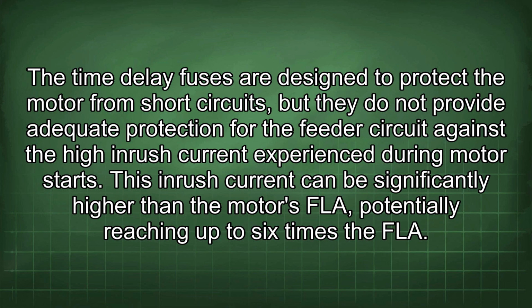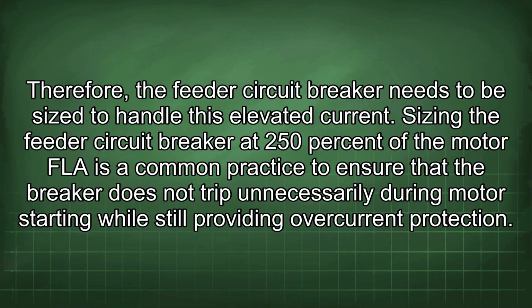This inrush current can be significantly higher than the motor's FLA, potentially reaching up to 6 times the FLA. Therefore, the feeder circuit breaker needs to be sized to handle this elevated current. Sizing the feeder circuit breaker at 250% of the motor FLA is a common practice to ensure that the breaker does not trip unnecessarily during motor starting while still providing overcurrent protection.